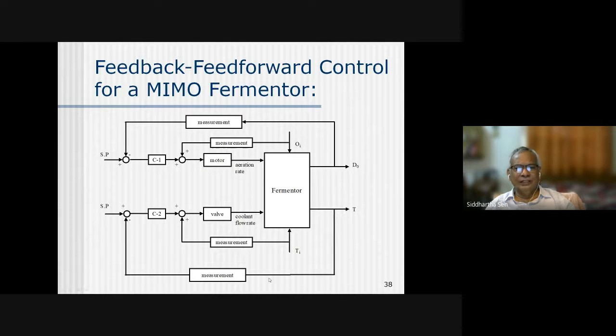Similarly, the temperature is measured and compared with the set point temperature. This is another PID controller, which gives the command on the valve, to open or close the cooling valve, or to what percentage, thereby varying the coolant flow rate. But you can see this is a feed forward scheme.